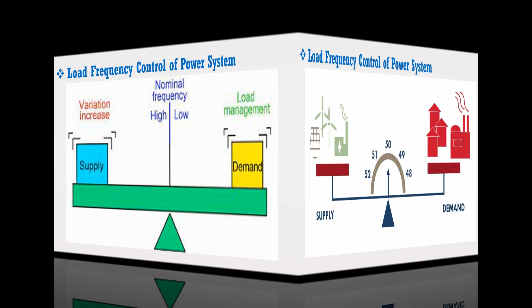In this situation, governor senses this decrease in speed and sends the signal to turbine to open its valve in order to increase the power generation. When generated power and increased load demands are equal, the system frequency comes to the stable value of 50 or 60 Hz. Similarly, whenever load is suddenly decreased, the system frequency suffers from overshoot. Governor senses again this increase in frequency and sends the signal to turbine to close its valve to some extent in order to reduce the power generation. Now again, when the generated power and the reduced load demand are equal, system frequency will come again to stable value of 50 or 60 Hz.